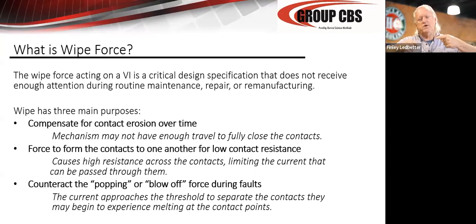Every breaker in the instruction book will have two lines aligned. It says when they're misaligned, replace it. Or it can be like this, and it says whenever it reaches here, replace it. Sometimes you have to physically measure with a scale. Every instruction book for every circuit breaker tells you how to measure wear. Wear is the number one killer of a vacuum interrupter.